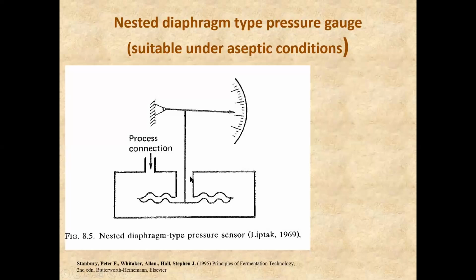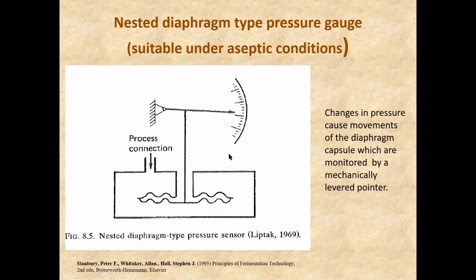Here you can see a diaphragm material. This is connected to the process of the liquid or the gas for which you want to measure the pressure, and you can see again here is a pointer and a calibrated scale. Changes in the pressure cause movements of the diaphragm capsule, which are monitored by this mechanically levered pointer.